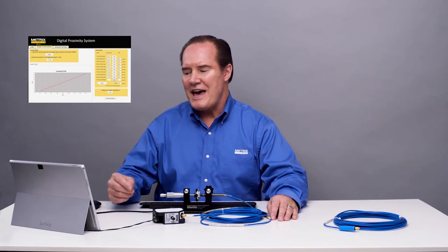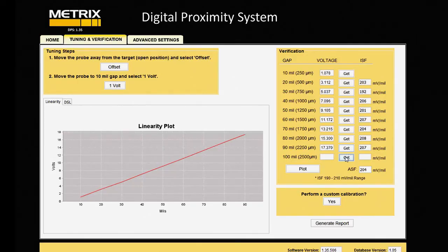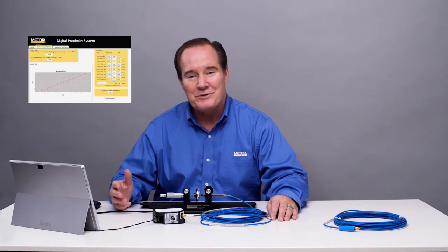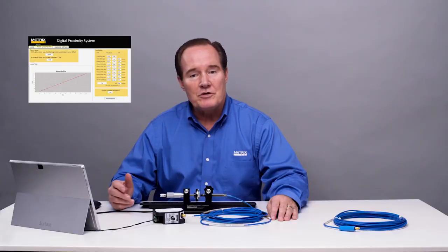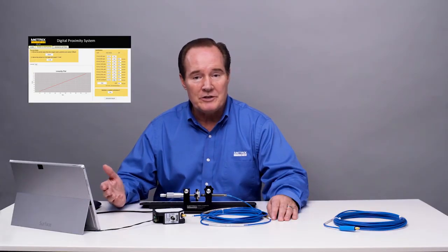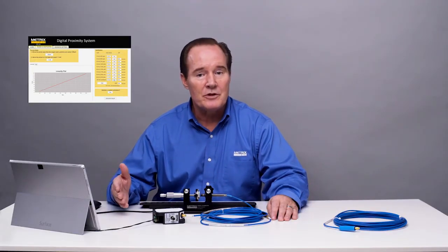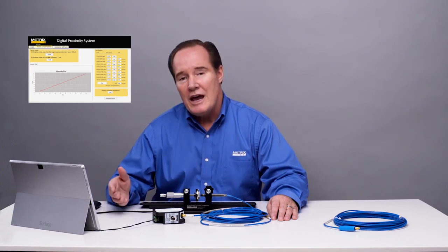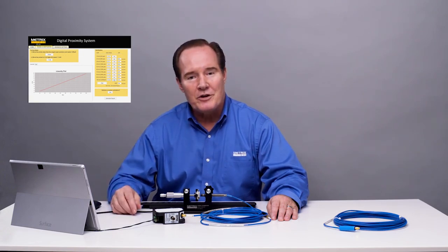All right, we got our last data point, and we see that the data from 10 to 90 is well within specification. The last point is out, but per API, it's from 10 to 90 that we measure, the 80 mil range, and that's very satisfactory results. And it shows that we can trim a cable, take 2 meters off, reconfigure the system for a 7-meter system, and it will get a satisfactory result with a custom calibration. Thank you very much.